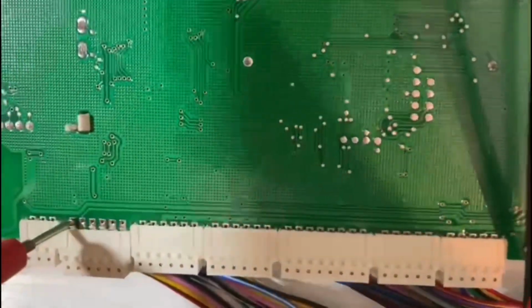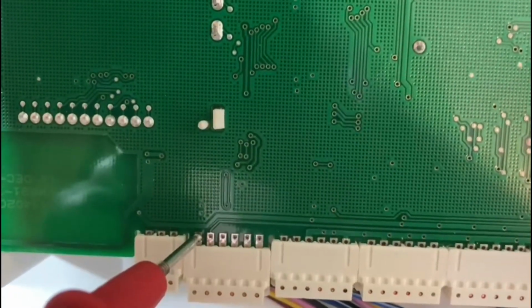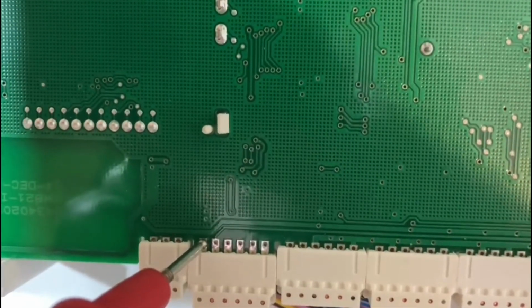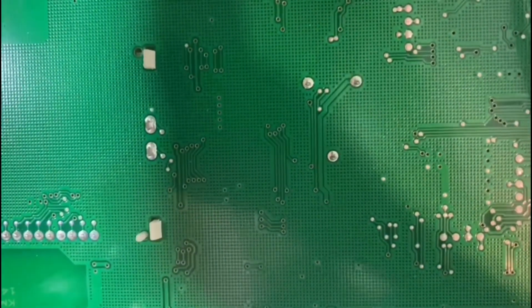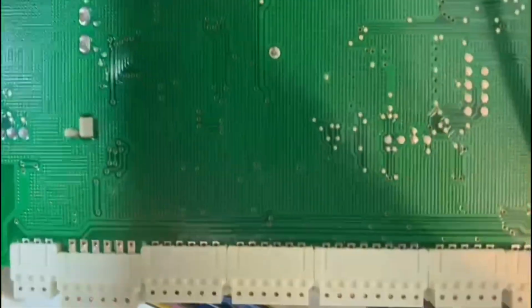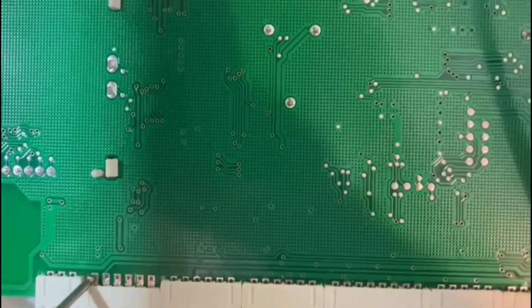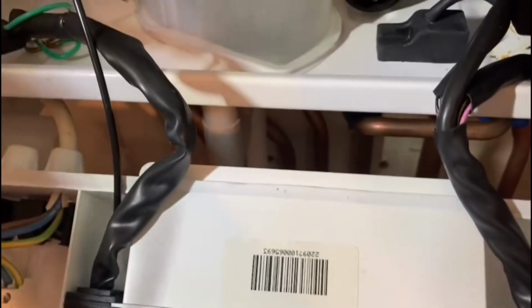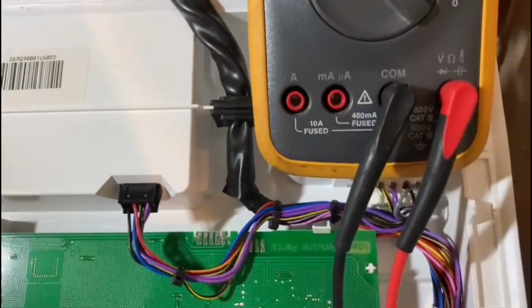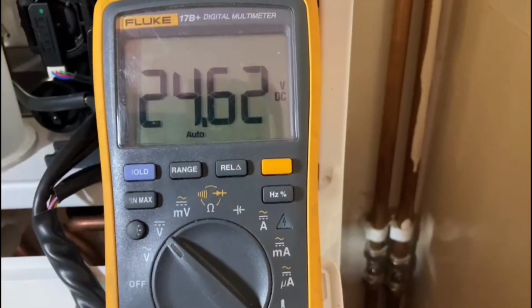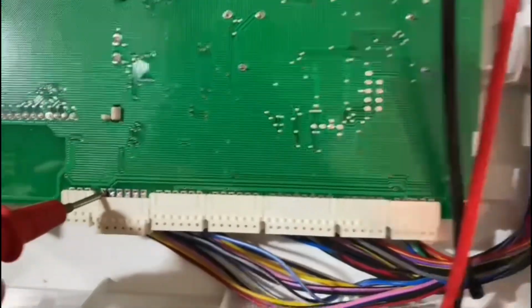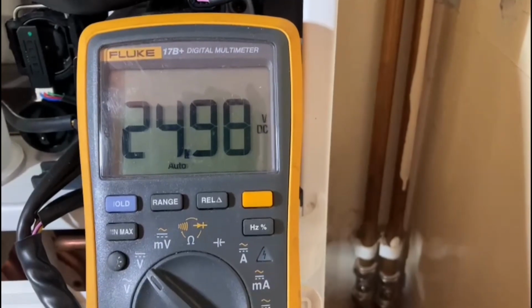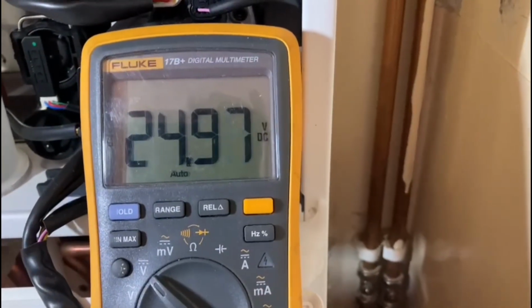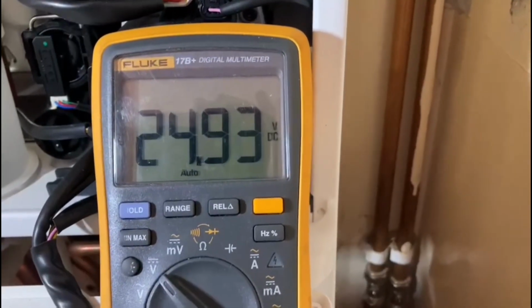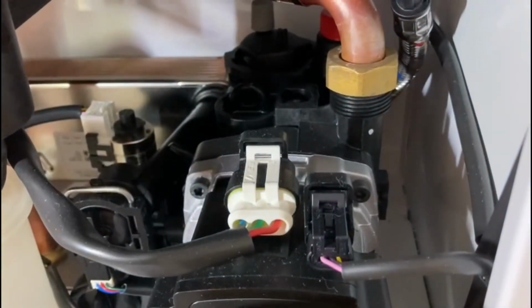So I have my positive red probe on the 24 volt supply on the circuit board, which are these two here, and I've had to just jam the earth on there to show you, and as you can see, we're getting 25 volts. If I change it to the other one, there's two, I'll put it on this one - again you'll see there's 25 volts. That should always be there. You should always be getting that from the circuit board, which sends power to the motor, to the coils.